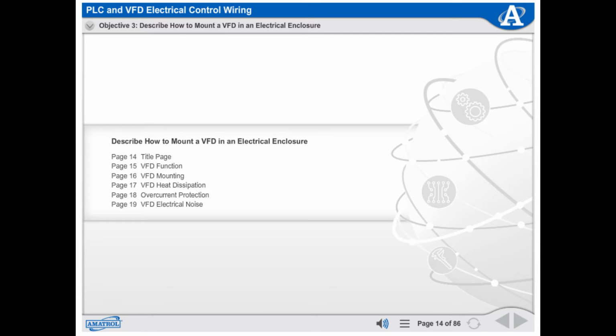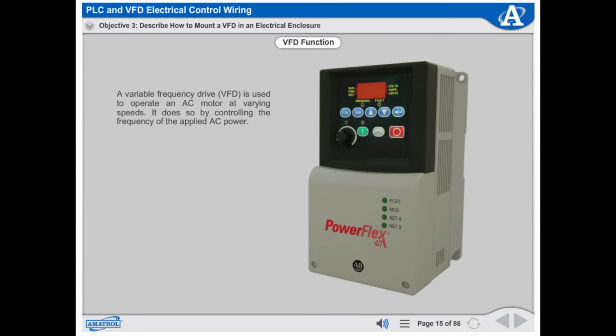Describe how to mount a VFD in an electrical enclosure. A variable frequency drive, or VFD, is used to operate an AC motor at varying speeds. It does so by controlling the frequency of the applied AC power. Major advantages of using a VFD to operate an AC motor include programmable motor acceleration and speed control.